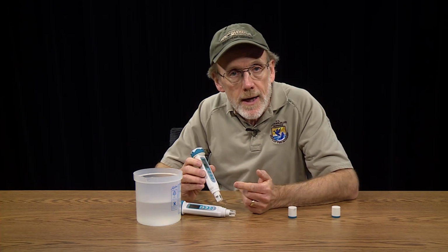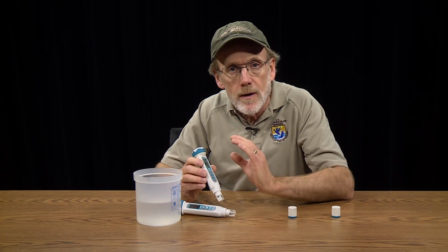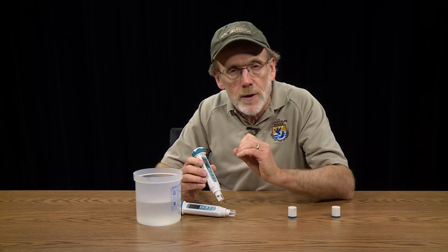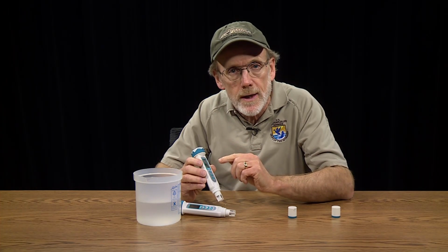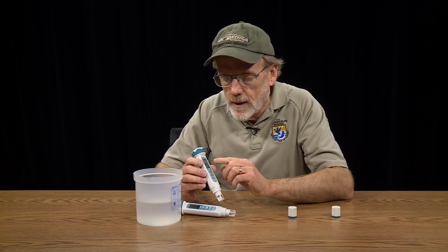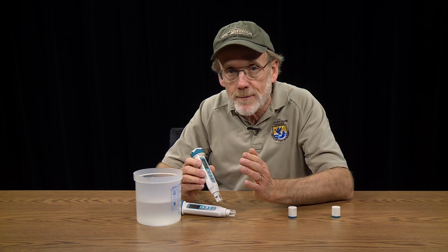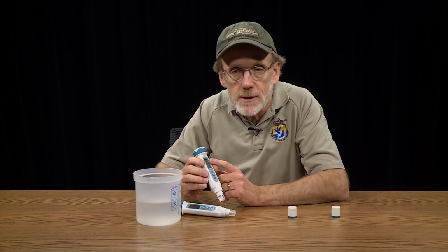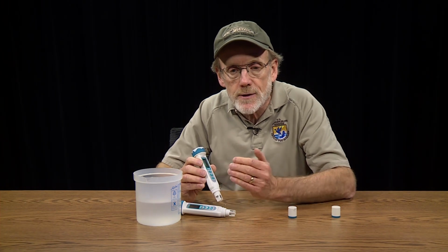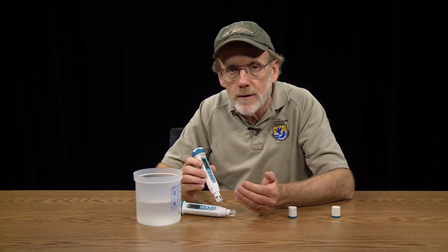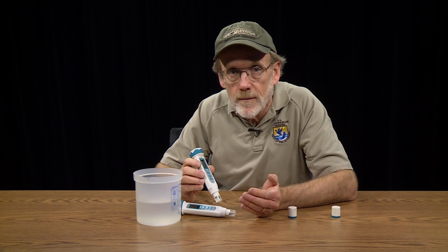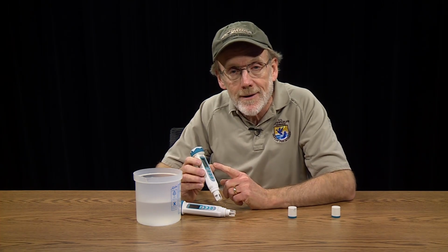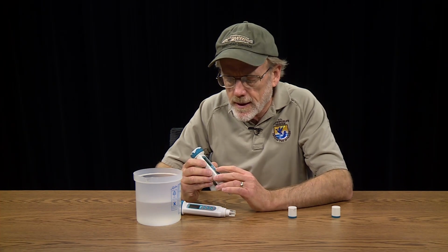So in this case, this was saying, do not adjust the temperature, make no changes to your original reading, despite the differences in water temperature and specific temperature. So what you see displayed is the actual conductivity not adjusted to some reference temperature. So that would be ambient conductivity. So let's look at the other one.